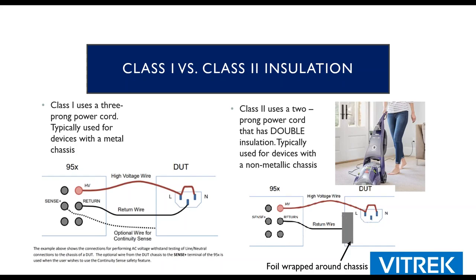But remember, to do a Hipot test, you still need 2 conductors with an insulator in between them. So you have to kind of create that second conductor in some situations. This is also common for photovoltaic cells when you're testing them. You're going to connect to positive and negative in that case, or line and neutral in a line powered application, and submerge it, wrap it in foil, wire brushes. I've seen all kinds of different things to simulate the areas where a person could touch and be able to complete that circuit to measure the current. Obviously, for a grounded cord, it's easier. You're able to use an alligator clip on the earth ground pin, or one of the breakout boxes that I can show you later.